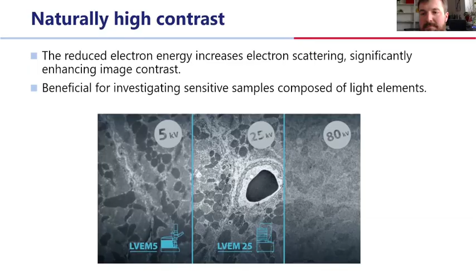To evaluate the image quality in electron microscopy, there are always two parameters which need to be considered. The resolution, of course, that's where the conventional big TEM excels, without any doubt. However, the second one, no less important, is image contrast, which is a really significant feature of low voltage transmission electron microscopes. This lack of contrast is a well-known phenomenon in transmission electron microscopy, but our low voltage system can deliver excellent contrast even for samples made of light elements, typically biological sections or other carbon-based materials like graphene.